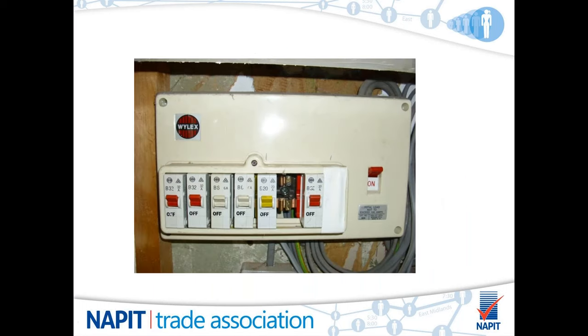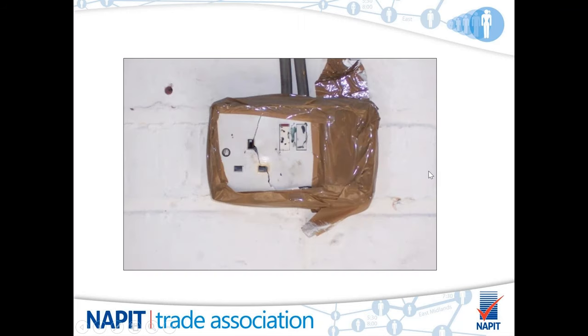In the picture shown on screen, it's showing an old rewireable consumer unit with the fuse carrier missing. With the fuse carrier missing, this is then causing an exposed conductive part. Also, to the far side of the picture, you can see that insulation tape has been used to prevent direct contact to an exposed conductive part. This is not a suitable method of preventing direct contact, and suitable blanks should be used to ensure safety. This is obviously shown in this picture.